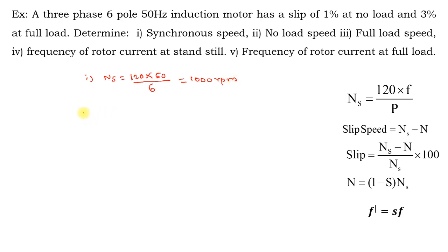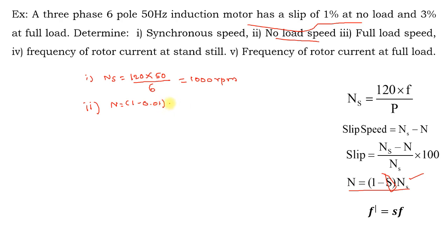Second, find no-load speed. The formula n = (1 − s) × ns applies. The motor has 1% slip at no load, so s = 0.01. Therefore no-load speed = (1 − 0.01) × 1000 = 990 rpm.